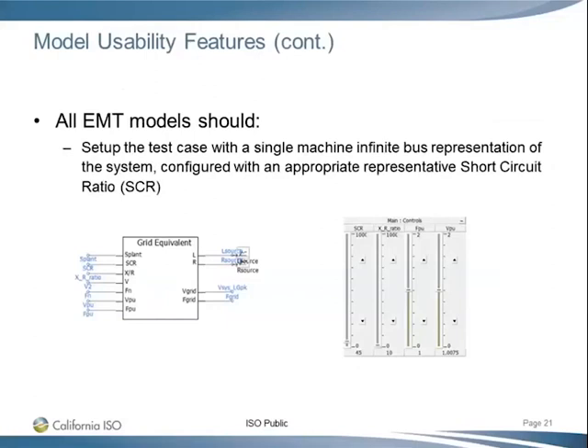And the model you submit should be set up as a single machine infinite bus representation of the system side. So it's a voltage source on the system side with some impedance that can be configured and adjusted to represent short circuit ratio. So this is an example. You have a grid equivalent there, and the SCR and the XR ratio are adjustable. So you see the slider on the right, so we can test the model under different SCR. Also, the reference can be adjustable. Next slide.